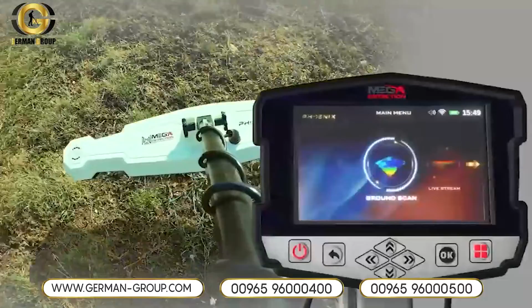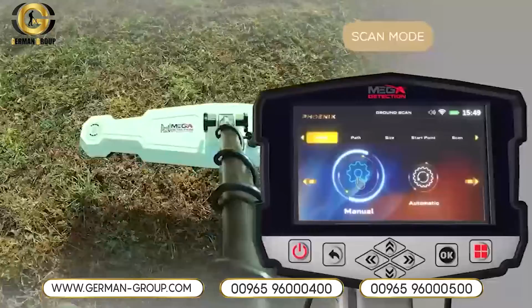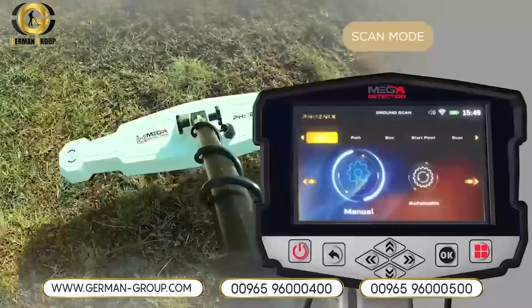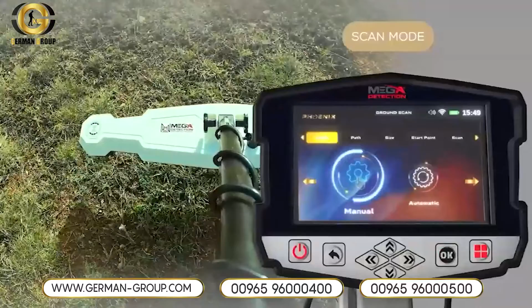Set up to display results on device screen. Scan mode. On this screen, the user can choose the scan mode, and there are two options. 1. Manual mode. The user performs the scanning process manually. That is, he records measurements manually at each scan point. 2. Automatic mode. In this case, the device will automatically scan the points without user intervention, as it scans the points automatically with an interval between each point. User only has to press on Start button at start of next scan line. To choose the appropriate scan mode, use the left-right arrow buttons, then press the OK button.